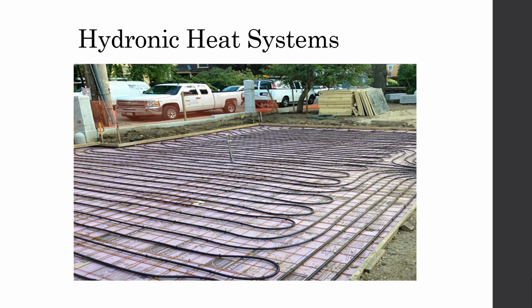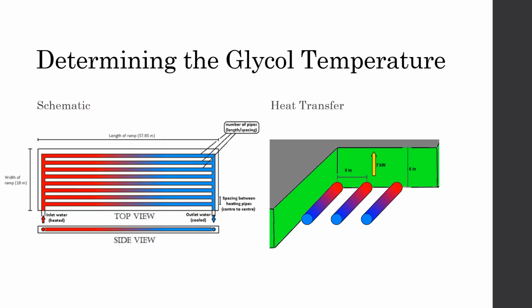We as a group felt that it was important that the fluid be reheated using a renewable and/or wasted heat source found on campus, to be expanded on later. It was calculated that in order to remove winter precipitation at a rate of 4.2 millimeters per hour, a constant heat transfer rate of 71.9 kilowatts was required between the flowing glycol and the ramp surface.